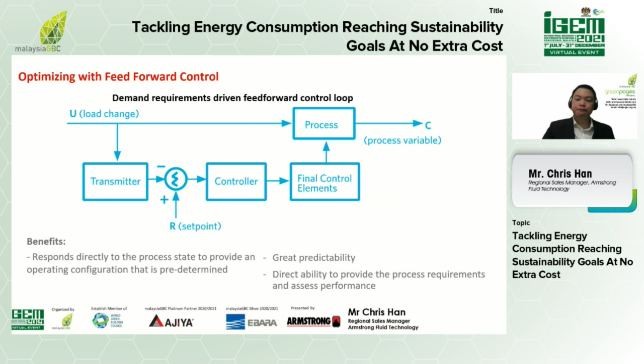The next topic is the retrofit, energy upgrade, or asset upgrade program. Whichever terminology you use, we should view it as a journey rather than a single step. At Armstrong, we prescribe a pump-first approach, where pump replacement is carried out early, in the first phase of the project, which is a relatively minor part of overall capital expenditure. We do this because it aids the data collection phase, and the data collected from operation helps inform future equipment decisions. With accurate data on the system of operation, in many instances, right-sizing the replacement equipment means selecting smaller and less expensive components.